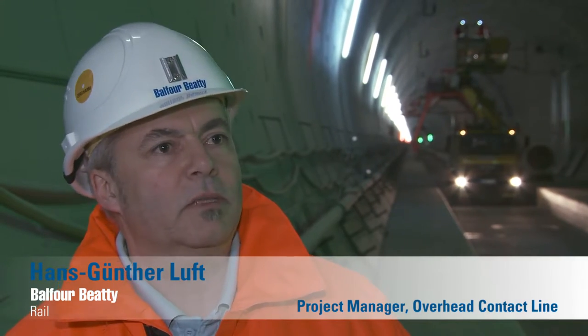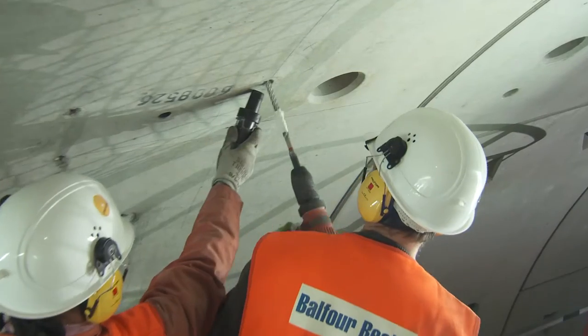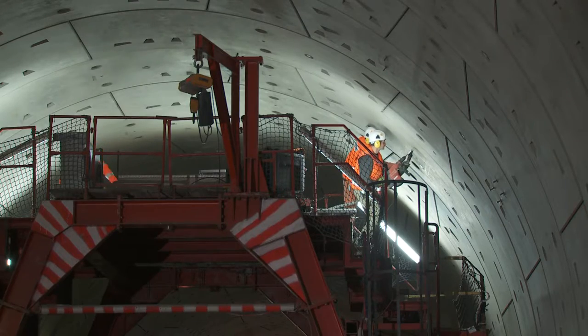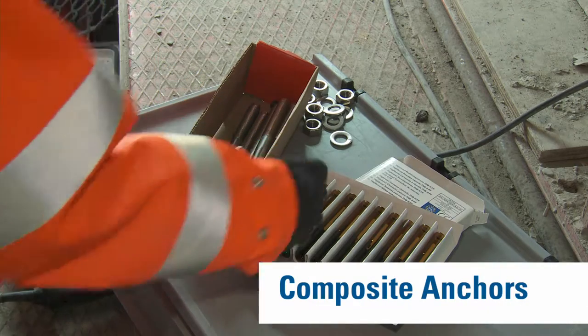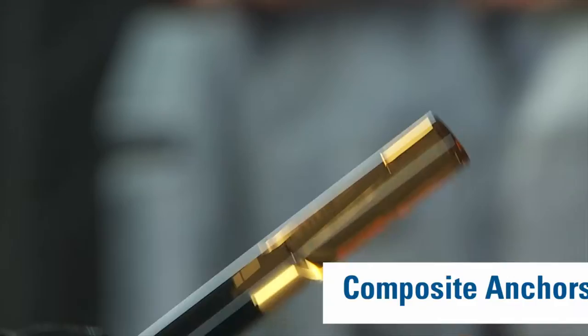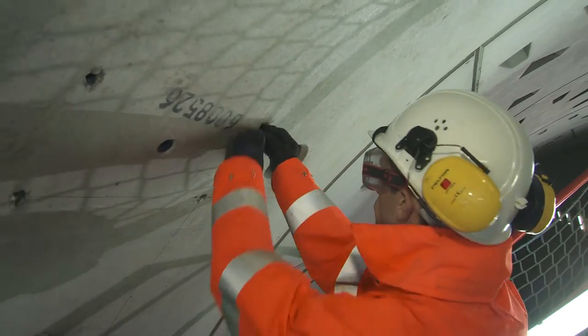All the components need to be drilled in this way. For components exposed to very high cutting forces, we use a composite anchor to absorb the energy. The cartridges on the composite anchors contain two chemicals which react with each other the moment the container is destroyed. The threaded anchor is glued into the concrete within a very short time. This connection is so stable that a passenger car could be hung from it.